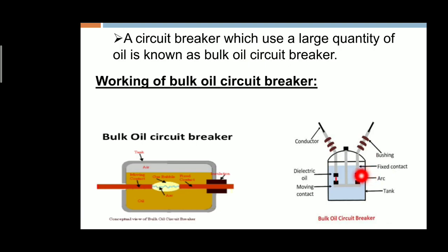Due to that arc, some heat energy is developed near the arc. Due to that heat energy, the surrounding arcing oil is converted into gas bubbles. By using these gas bubbles, we extinguish the arc within a very short time.